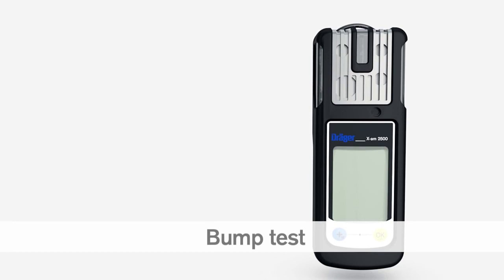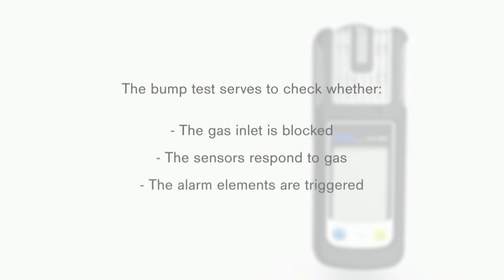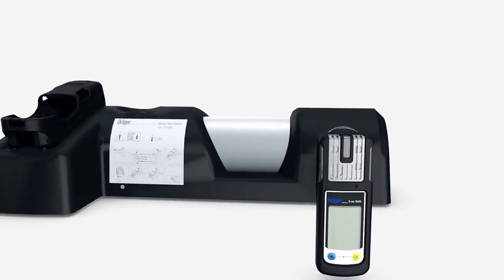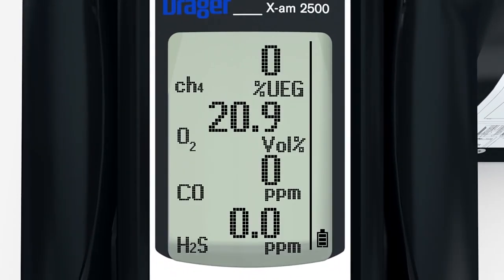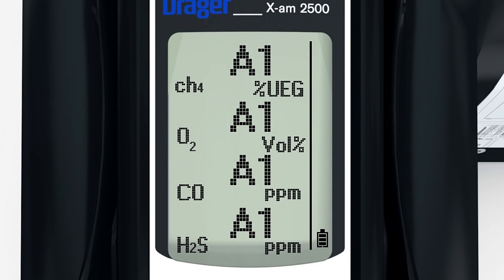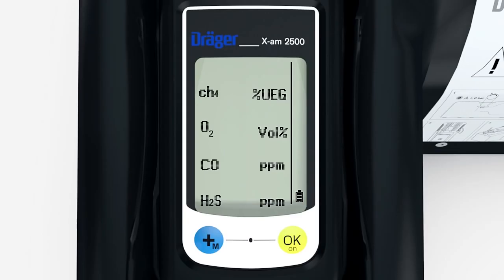You must carry out a bump test of your X-am 2500 in accordance with the national regulations and guidelines in force. The bump test serves to check whether the gas inlet is blocked, whether the sensors respond to gas, and whether the alarm elements are triggered. Place the switched-on instrument inside the calibration cradle, where it will be recognised automatically. Gas now flows automatically over the sensors and the alarms are shown. If the bump test passes, OK will flash in the display. If a functional test does not take place correctly, a channel error is shown for the sensor or sensors, and the device will have to be calibrated and possibly repaired.